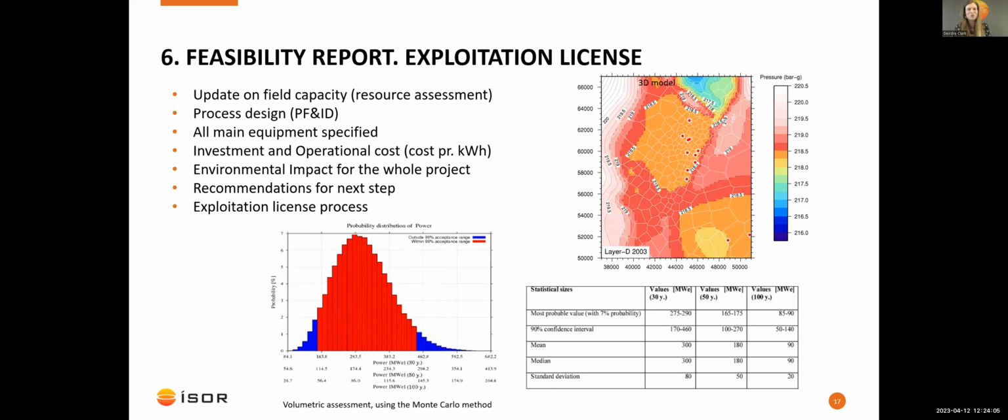So going 20 to 50 megawatt steps rather than all of a sudden to 100, 200, 300 megawatts in one go. By thinking from a smaller scale, you're de-risking the chance of over-exploitation and over-investment. An example of what not to do is The Geysers in California. They planned for a 2,000 megawatt power plant, but the system in the end sustains about 700 megawatts. This did not need to have happened. You could have done a stepwise thing of going maybe 200, 300, 400 and up from there.